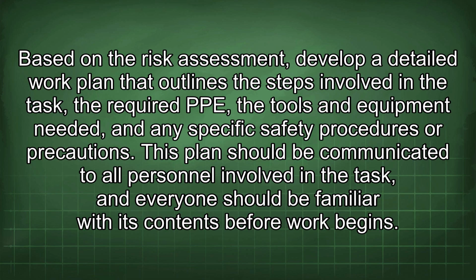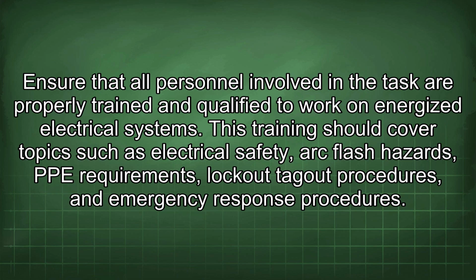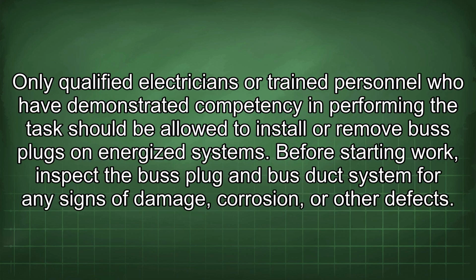Ensure that all personnel involved in the task are properly trained and qualified to work on energized electrical systems. This training should cover topics such as electrical safety, arc flash hazards, PPE requirements, lockout-tagout procedures, and emergency response procedures. Only qualified electricians or trained personnel who have demonstrated competency in performing the task should be allowed to install or remove bus plugs on energized systems.